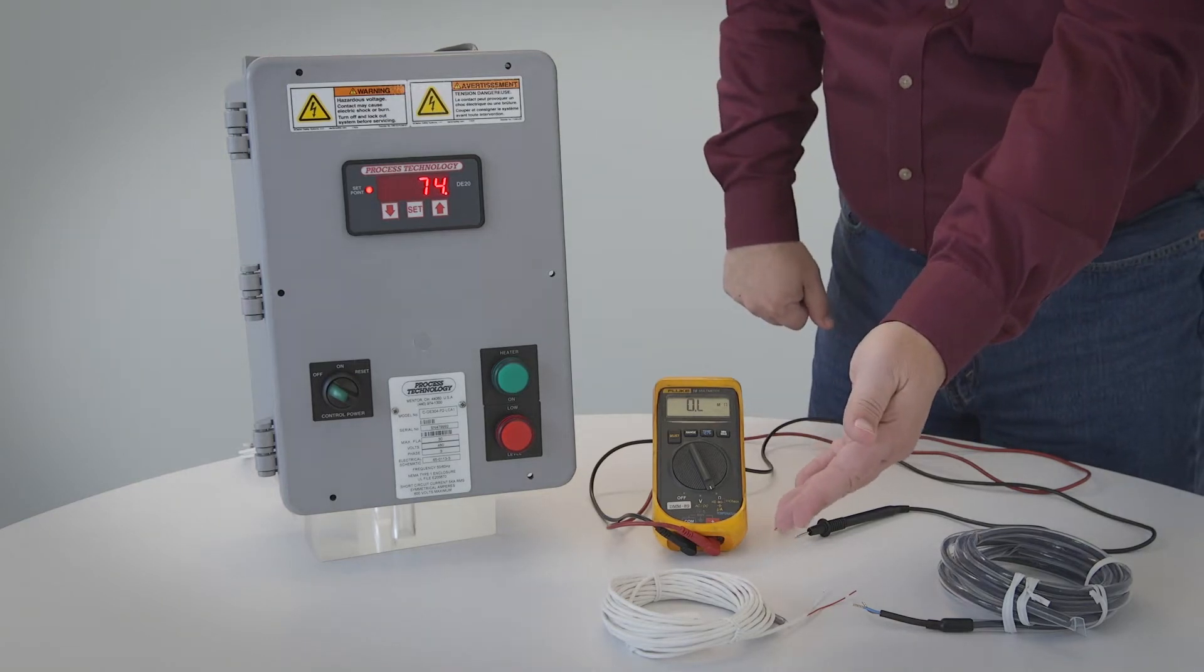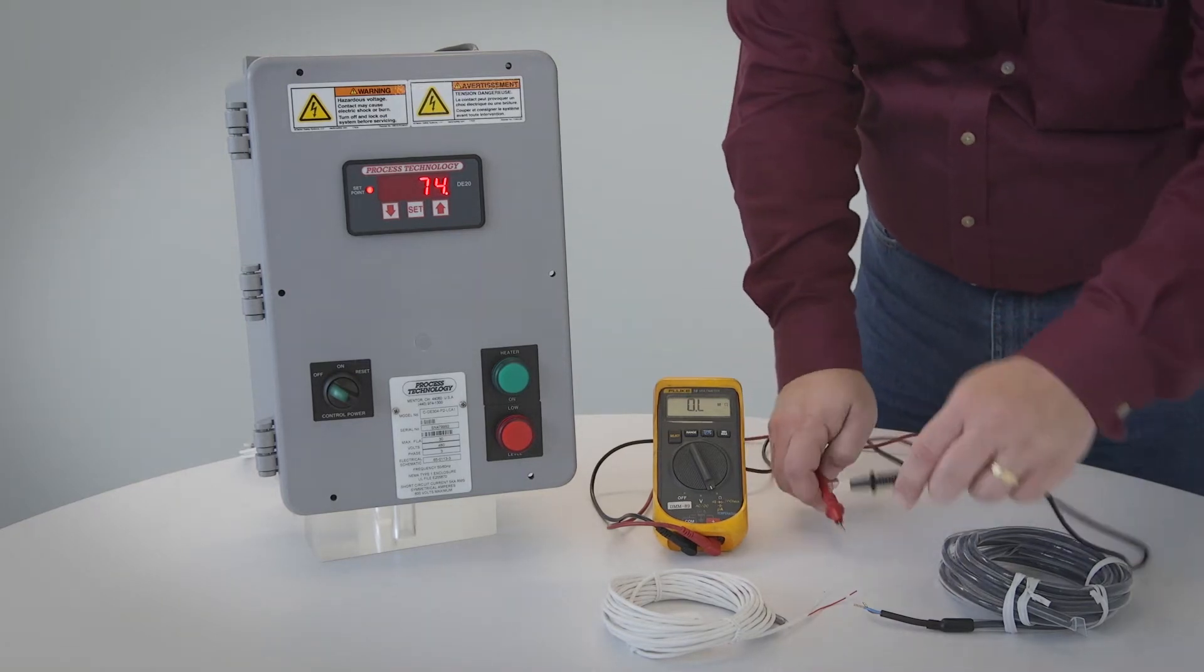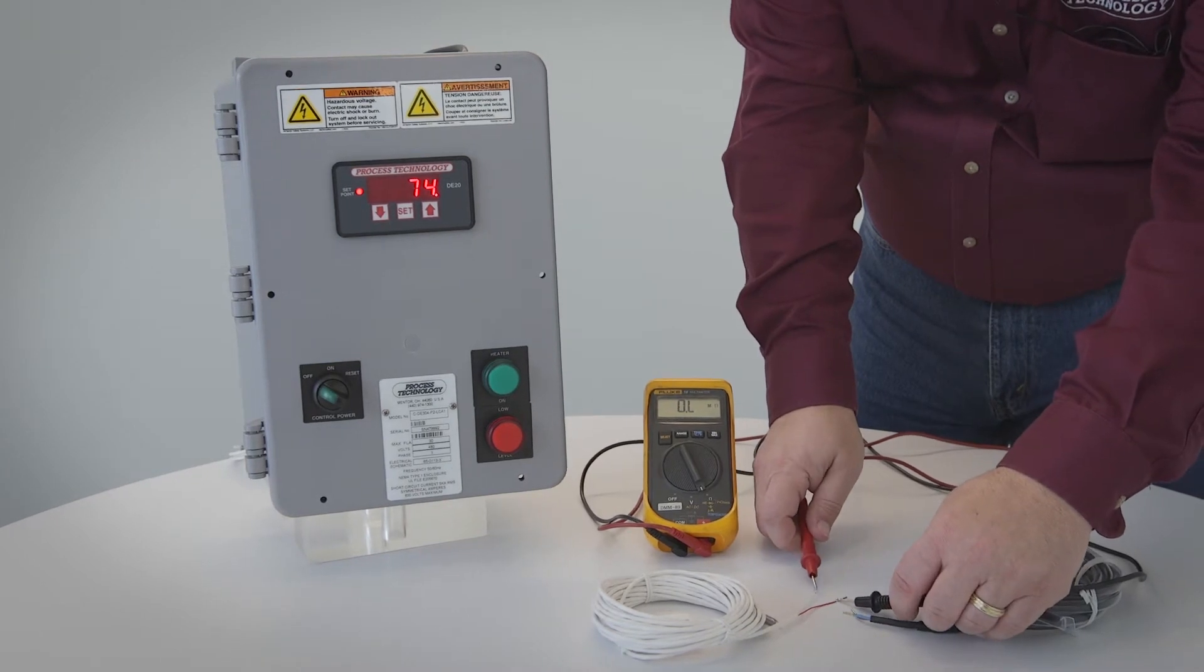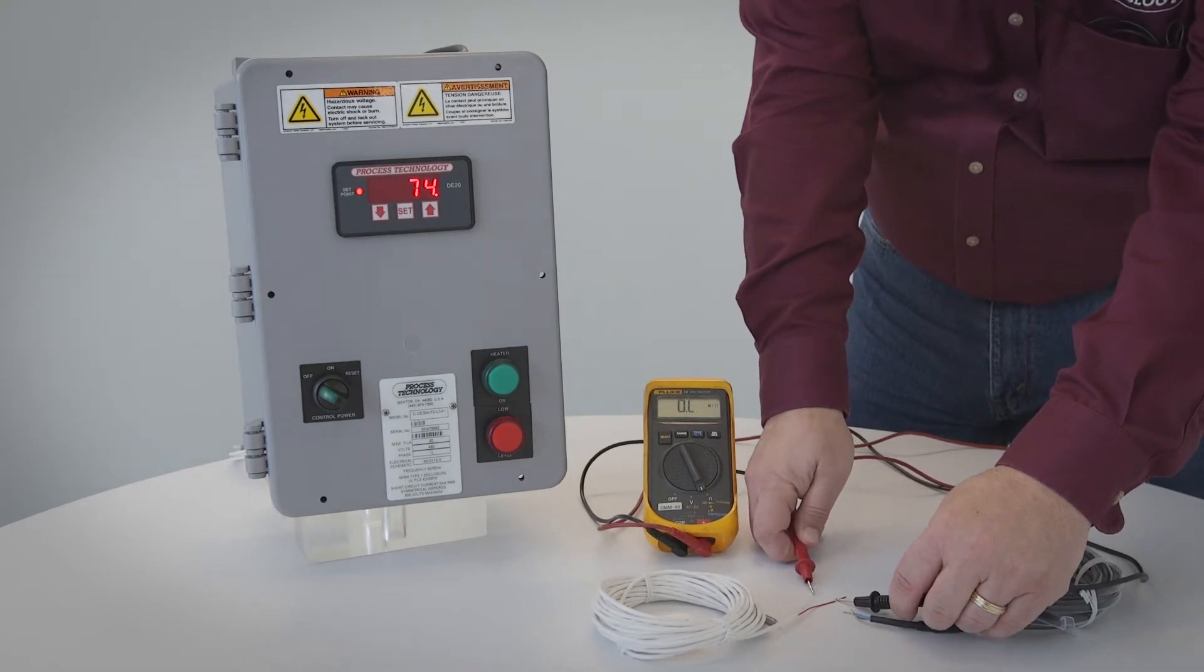The standard temperature sensor is a 1,000 ohm RTD. This sensor should measure somewhere around 1,090 ohms at room temperature.